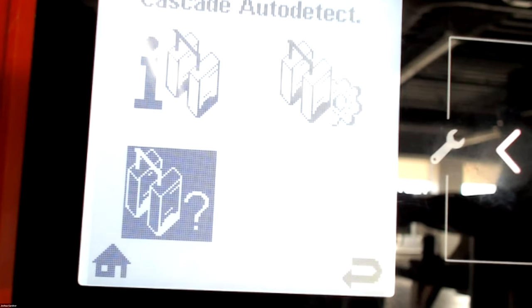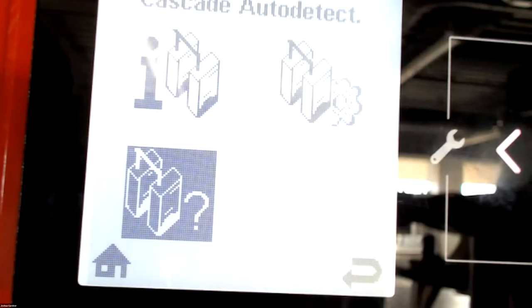When we first install the cables and we get everything up and running, it'll auto detect, go out, and it will detect how many boilers we have. So if we have 3 boilers on there, we hit the auto detect, it'll go through, look for those boilers, it'll come back and say, you have 3 boilers installed, is this correct? Press okay, if not, go back. So we press okay, and then from there, we're connected, we go make our setting adjustments. Once you make any setting adjustments on the cascading, you need to go back in and auto detect, and that actually saves your settings once you go through and auto detect again.